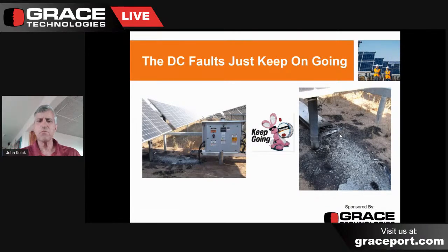Here we see a system where we've had a raceway on the DC system coming in that completely melted into a puddle of molten aluminum. What happened here is it was a relatively low capacity fault. However, it continued to burn for so long that it melted all the enclosure. And by the way, this fault got started by mice, actually. The mice chewed through the wires and initiated an arcing fault. And you can see it lasted long enough to actually melt the entire raceway.